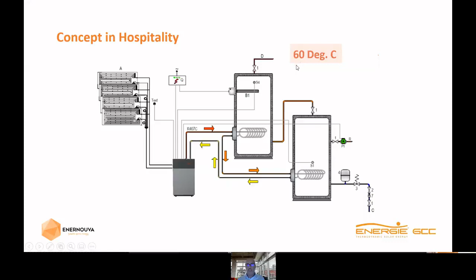So the cycle will go on until the water meets the set point, which in a hotel is 60 degrees. Then it will stop and it will restart on a delta T that you can choose. Then we have the hydraulic line: the cold water supply coming before the secondary heat exchanger, the hot water return coming after the secondary heat exchanger but still on the preheating tank, the preheated water, and then the supply water to the building. This is a schematic of one module, and we can scale the solution to whatever needs we want, as long as the temperature of the water doesn't increase more than 65 degrees.